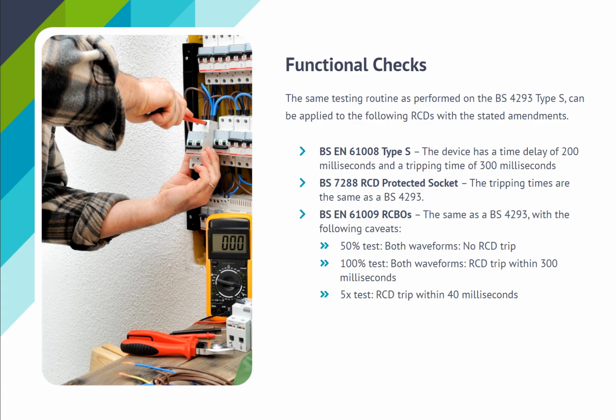BS EN 61009 RCBOs, the same as a BS4293, with the following caveats. 50% test, both waveforms: no RCD trip. 100% test, both waveforms: RCD trip within 300 milliseconds. 5x test: RCD trip within 40 milliseconds.